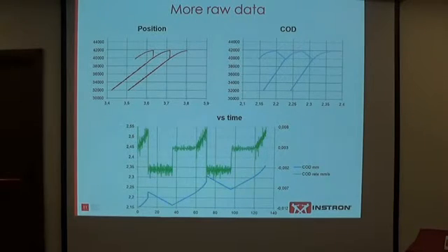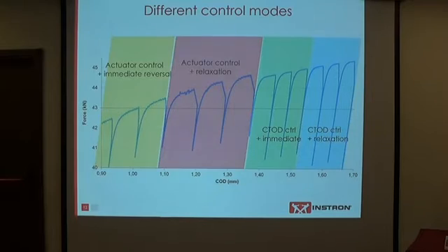So, well, good. Waiting for it to advance. Okay, so what I've just done to show you on one specimen at the same point, I've set up a very strange test here where I've got 4 different control scenarios. So this is what we'd be hoping for, just as standard, that we more or less immediately reverse. So we're loading up, and we turn around and go straight back. And you can see there is a distinct offset between loading and unloading.